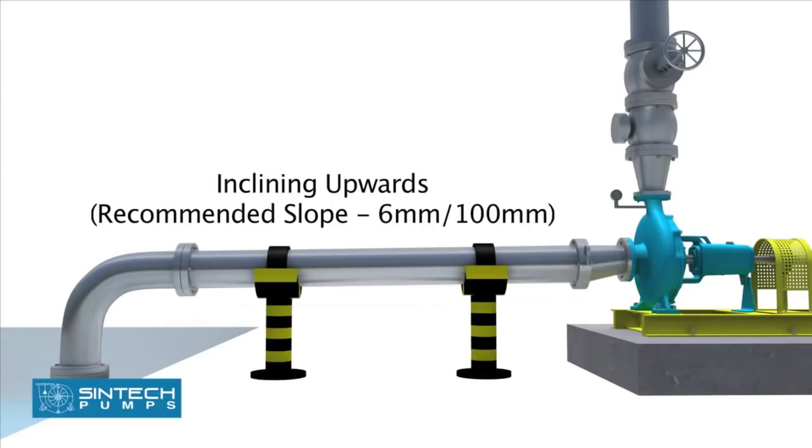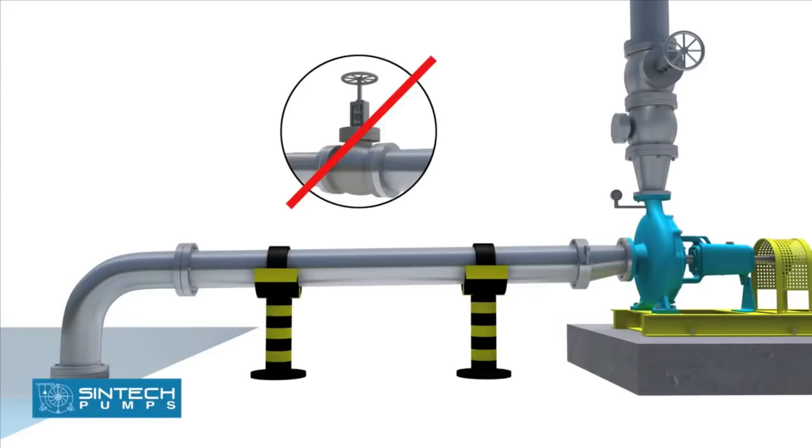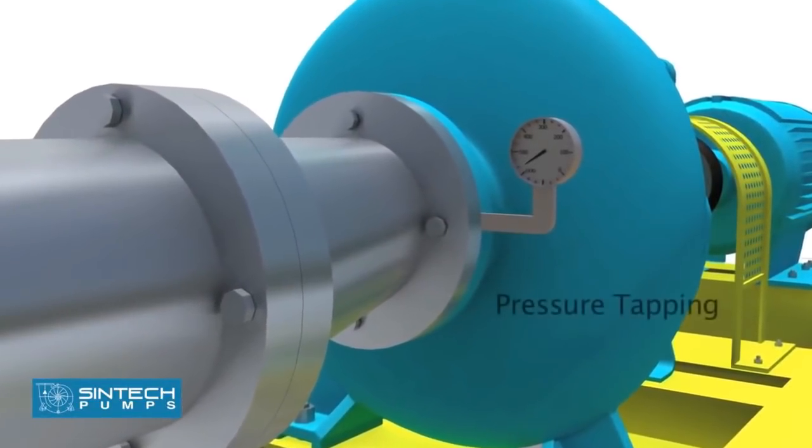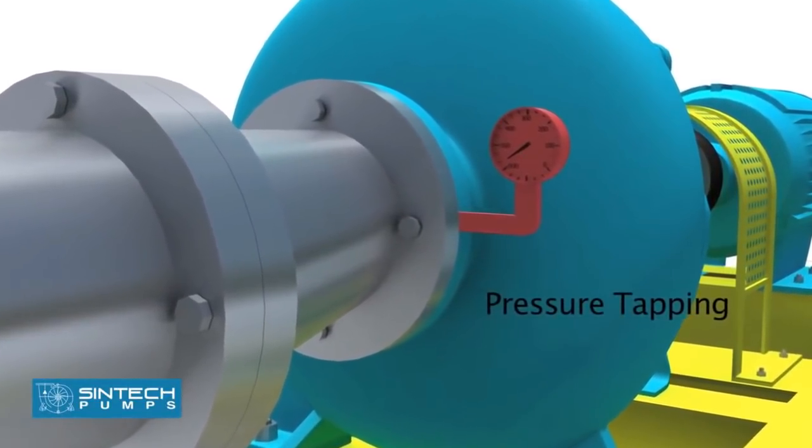All suction pipes should have a continuous rise to the pump suction inlet. Six millimeter per hundred millimeter slope is recommended. No isolation valve is recommended. There should be a tapping provided for installing a vacuum gauge in the suction line.